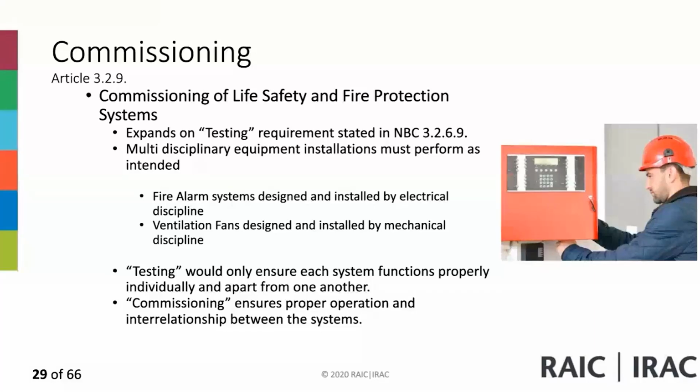Okay, 3.2.9 says, where fire protection and life safety systems and systems with fire protection and life safety functions are integrated with each other, they shall be tested as a whole in accordance with CAN/ULC-S1001, Integrated Systems Testing of Fire Protection and Life Safety Systems, to verify that they properly are integrated.